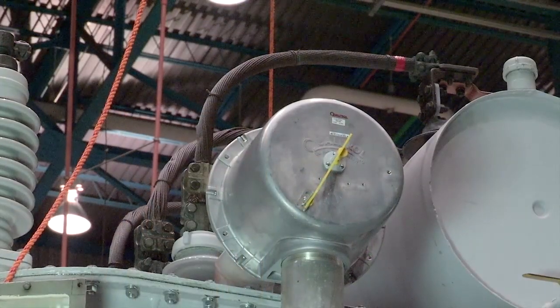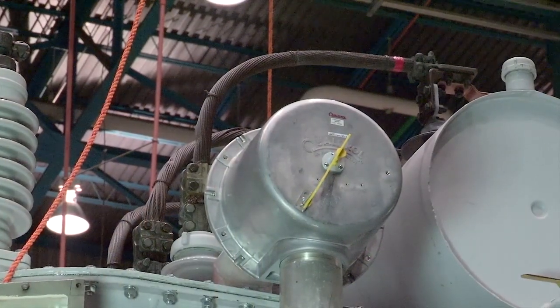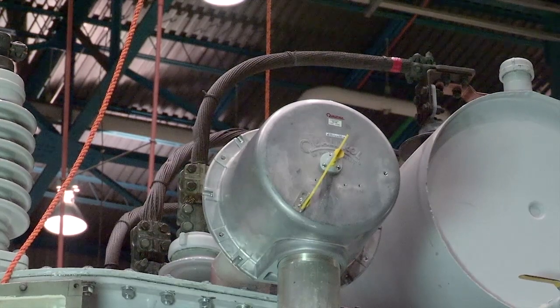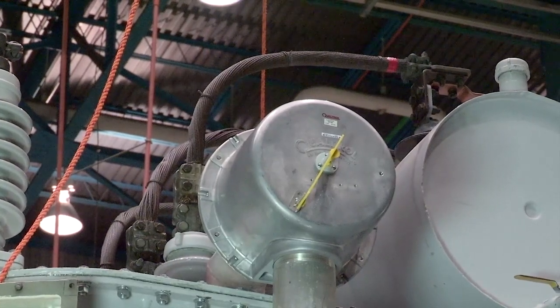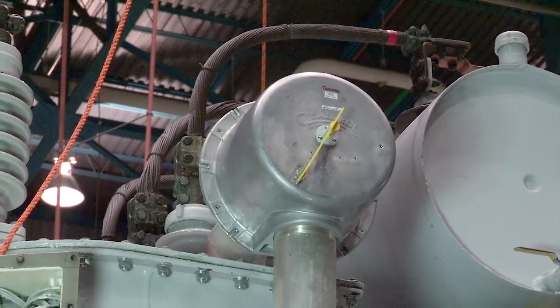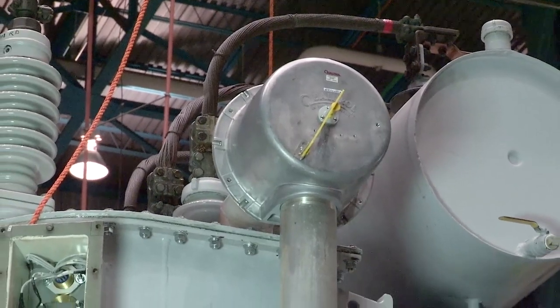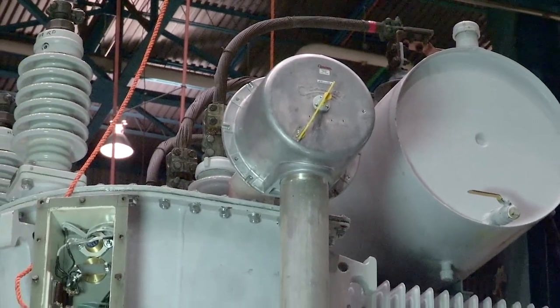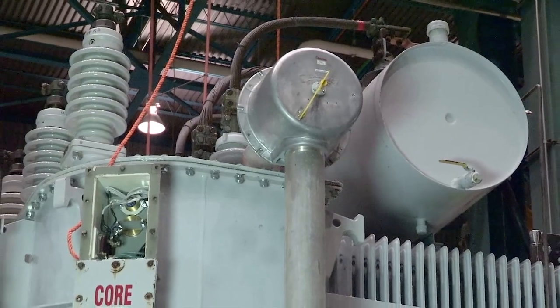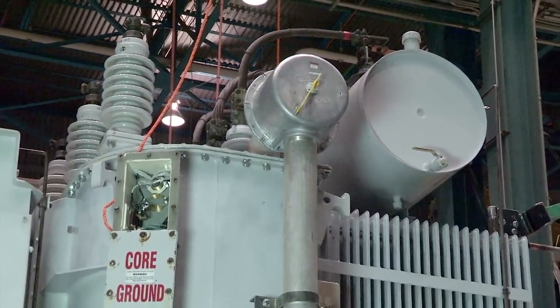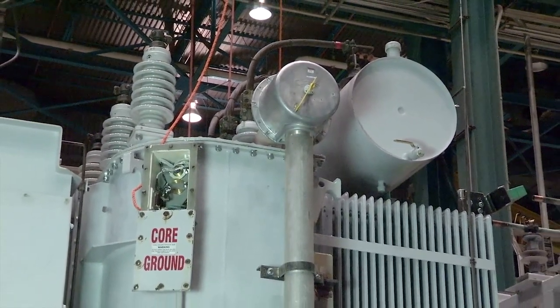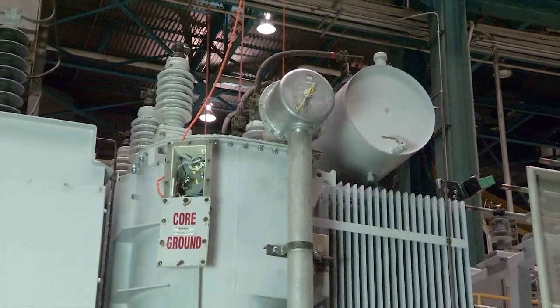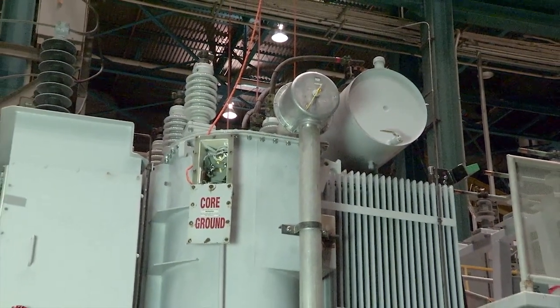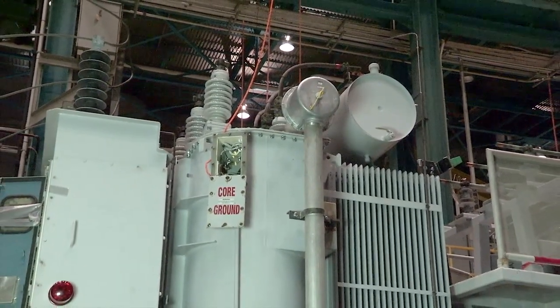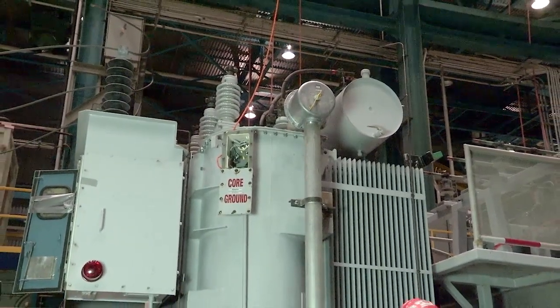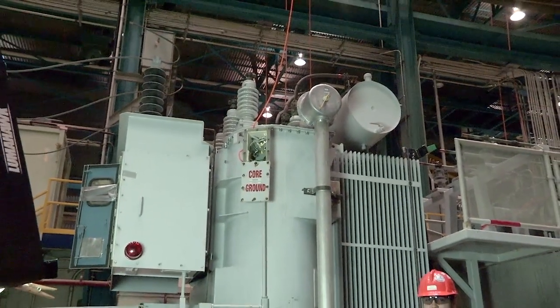Now we're looking at the Qualitrol. What you want to do is just inspect the Qualitrol, make sure the flags aren't up or anything like that, that it's seated and not leaking oil. A lot of people have a habit of leaving the valves closed, and Qualitrols do tend to go on these things sometimes. This one is a newer mod they put on them. They put an expansion chamber on it with an indicator, so you don't have to see the flag from a ladder up top. You can see it from the side here. And they equip it with a downpipe now, so it isolates your spill to one spot and not all over the whole area.